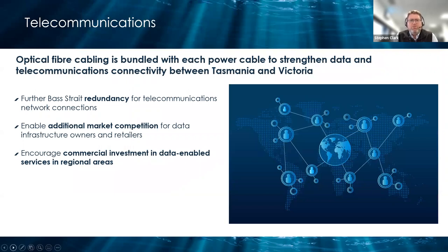We're bundling fibre optic cable with each of the power cables. That's required to make sure the control systems of the converter stations can talk to each other. But being optical fibre, there's plenty of extra capacity there, so we'll use that to further increase data capacity between Tasmania and Victoria, and add redundancy. We'll have two separate cables, adding to the two existing Telstra cables and the Basslink cable, increasing competition and availability of data for commercial provision.